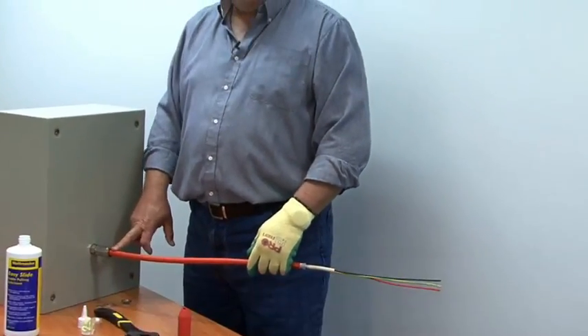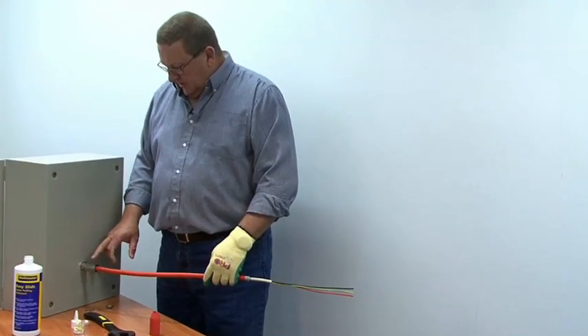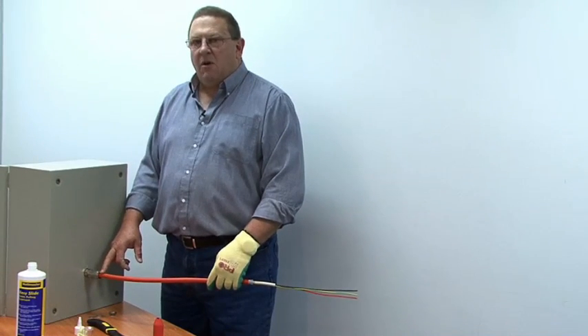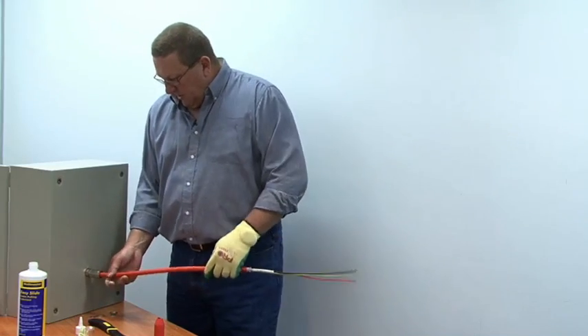If it's loose and sloppy here, then pull it apart and have a look at the length of your steel wire armour. That seal needs to be on the PVC. If it's not, and if you've left the steel wire armour too long, then the seal won't clamp up and it will be sloppy at the cable entry.